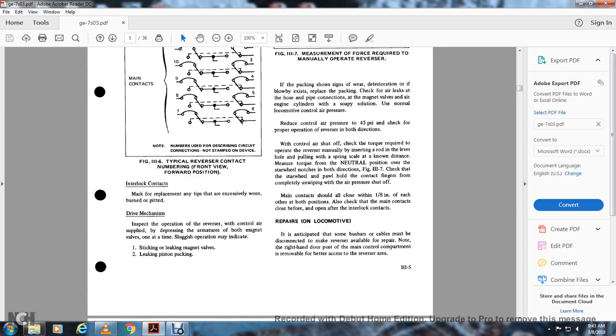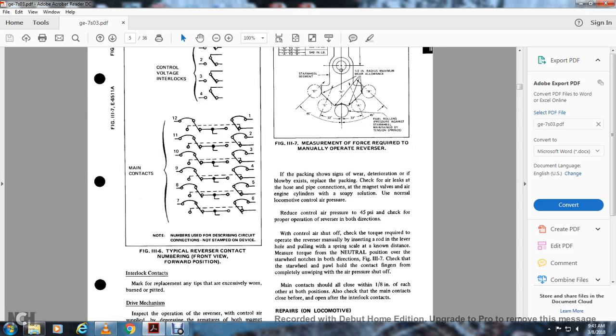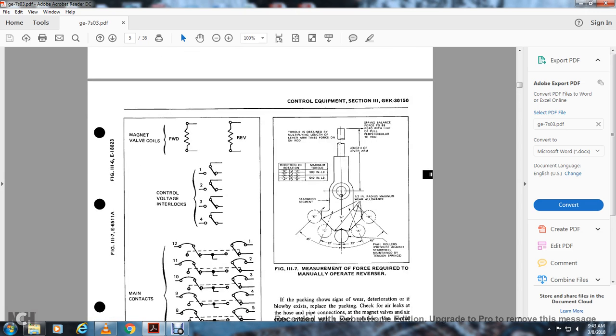Interlocking contacts: mark for replacement any tips that are excessively worn, burned or pitted. Inspect the drive mechanism, and inspect the operation of the reverser with the control air supply, depressing the armature of both magnet valves one at a time. Sluggish operation may indicate sticking or a leaking magnet valve, or leaking piston packing. Figure 3/7 is the measurement of force required to manually operate the reverser.